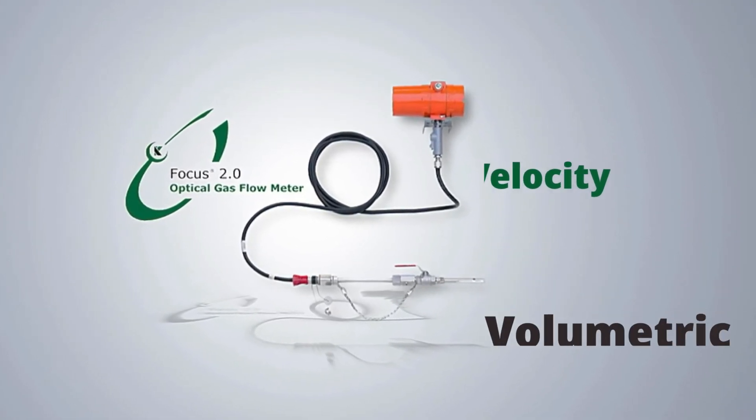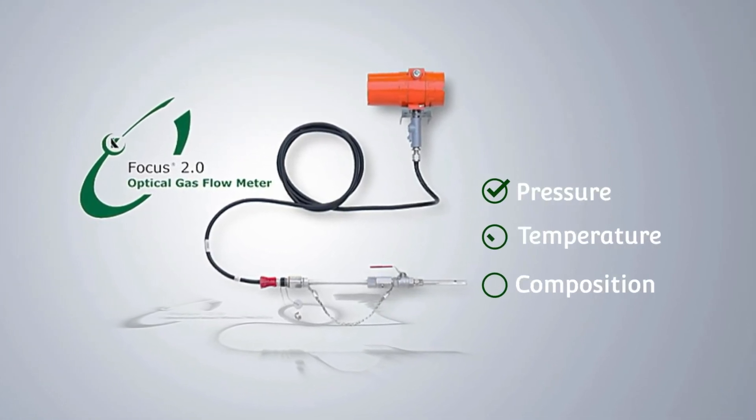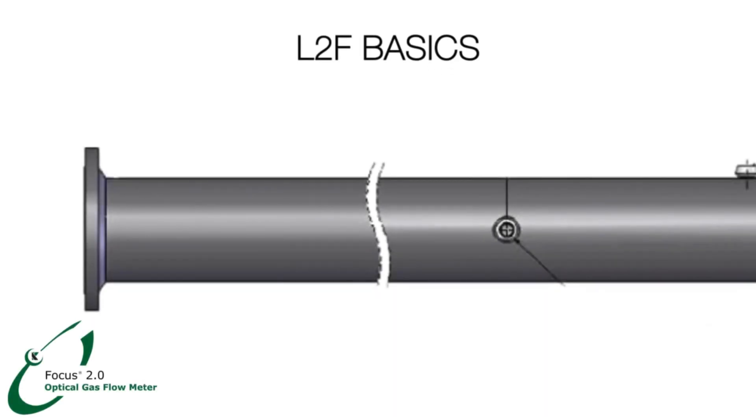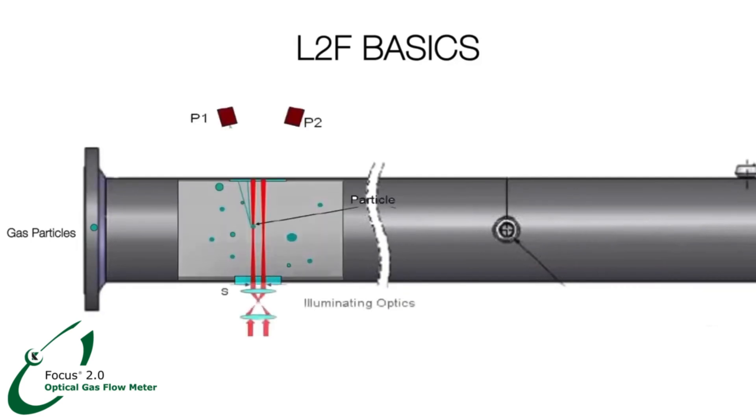The Focus 2.0 OFM delivers high accuracy independent of pressure, temperature, and gas composition. It is based on Laser-2-Focus (L2F) technology, where small particles found in any natural or industrial gas pass through two laser beams focused in a pipe by illuminating optics.